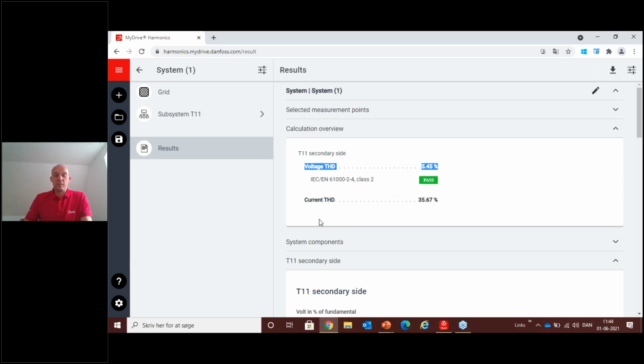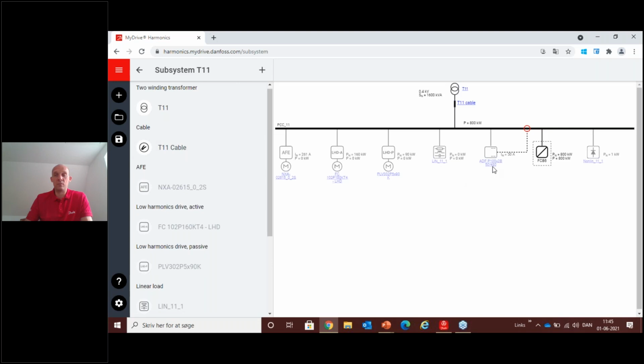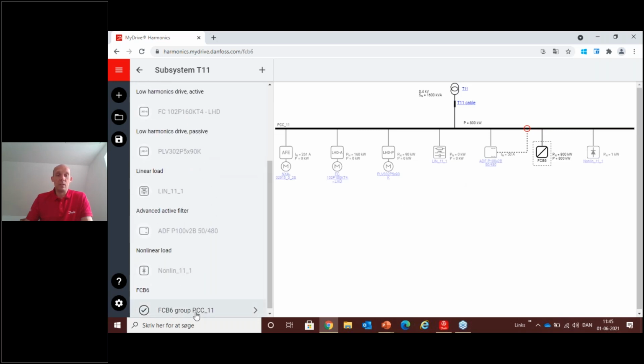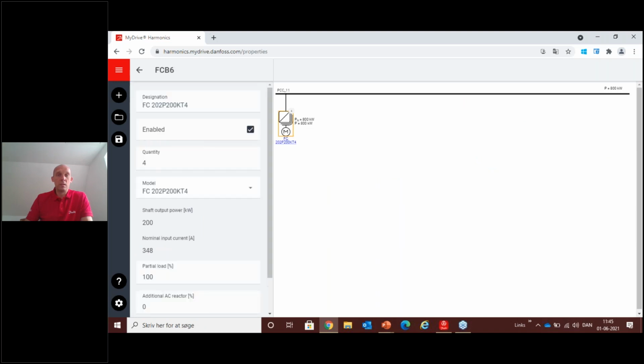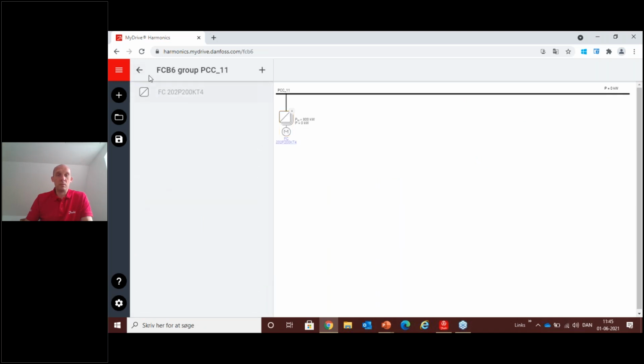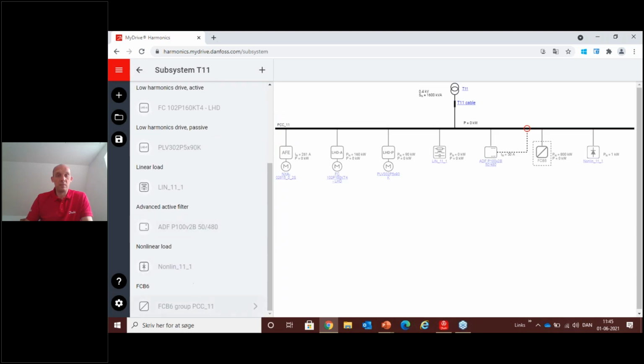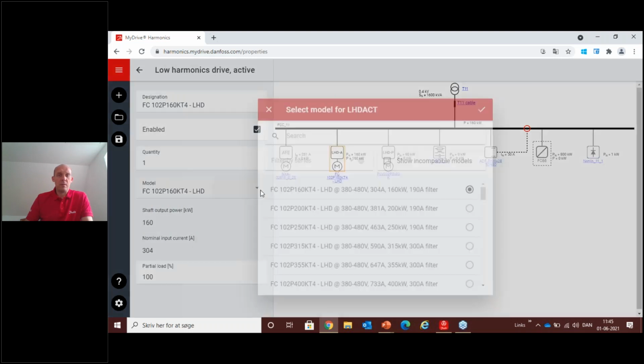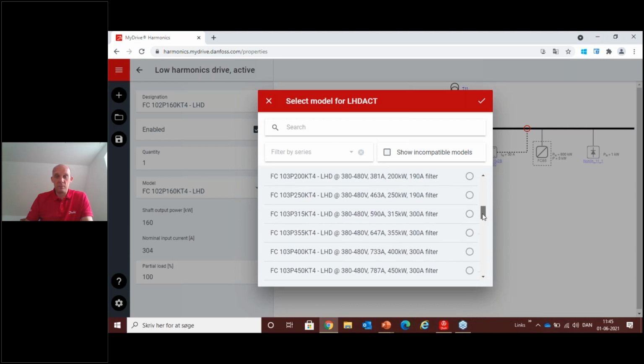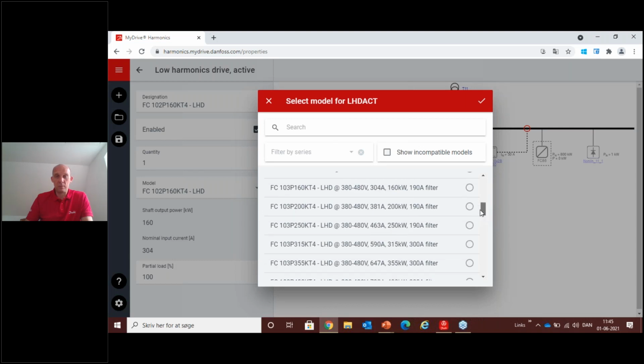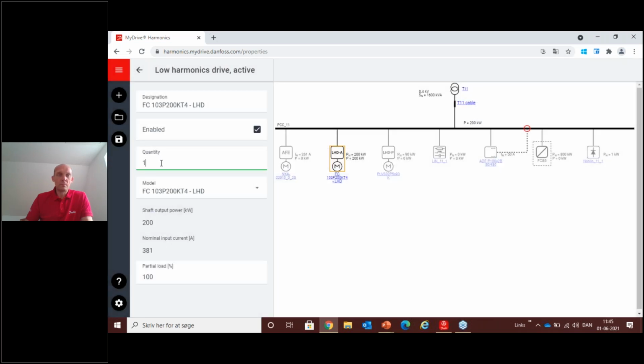As said, this tool is free for you to try out and run. You can go into your system and add different things to it. For instance, if I wanted to change the drive to be low harmonic, I could do that as well. I would go in here, disable those, and install low harmonic drives instead. So now I'll use low harmonic drives instead of standard drives to get the 5% current distortion, sorry.